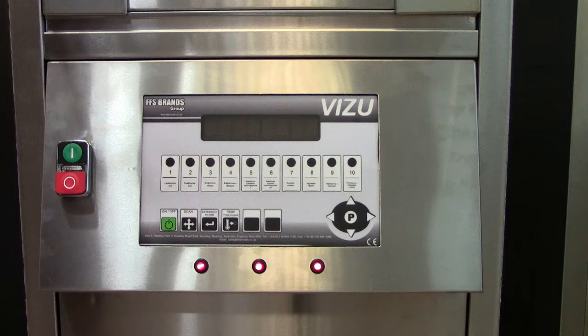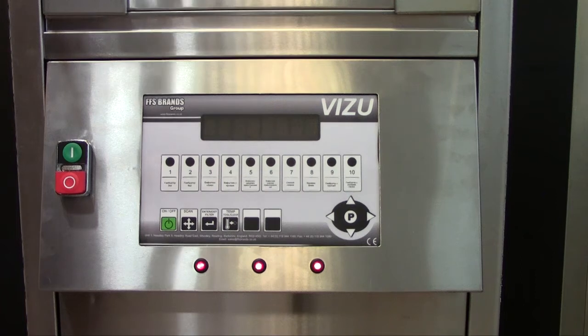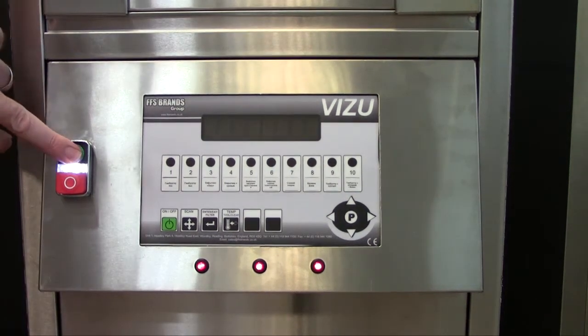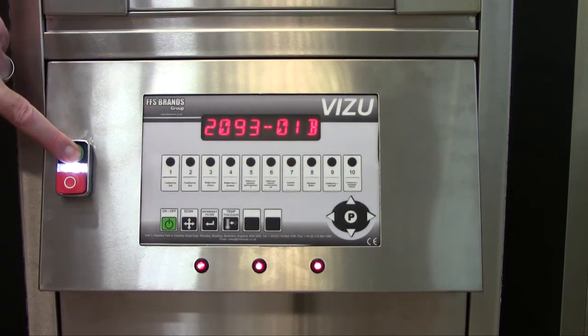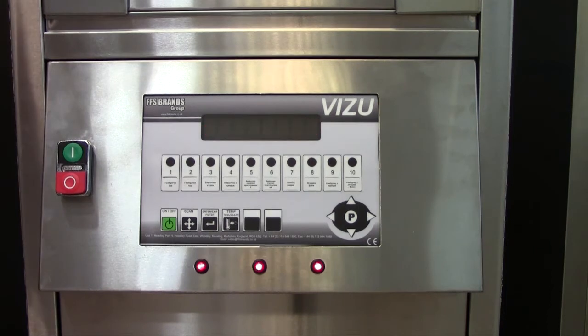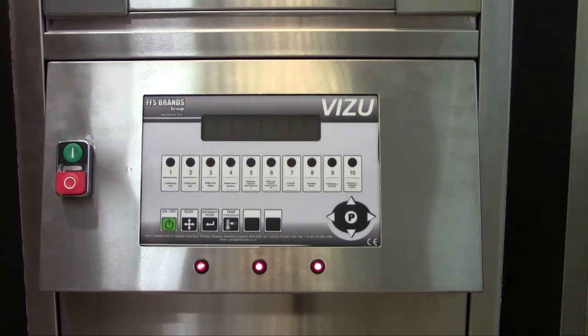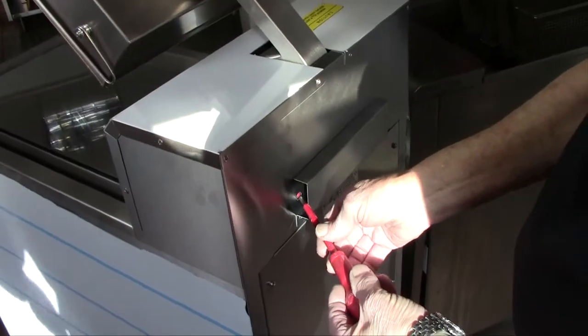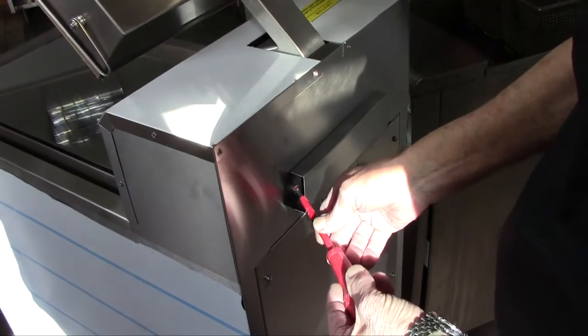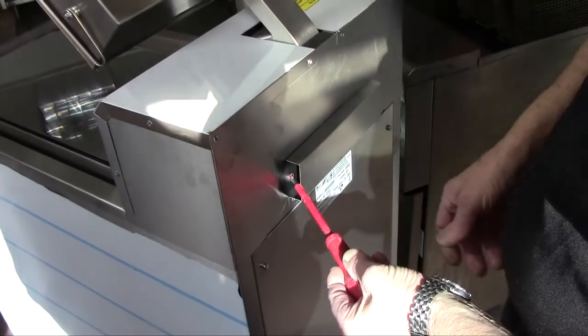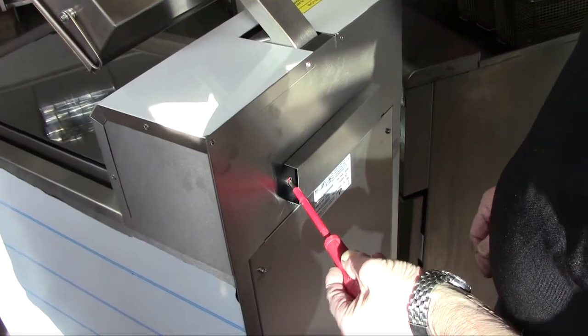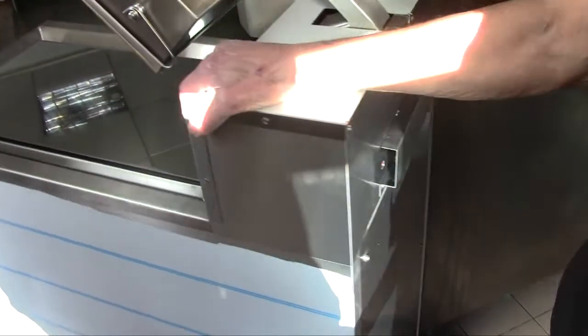If the problem still exists, as a check, press the start button, hold for 10 seconds and the display should come up. But on releasing it, if it goes out, then check the high limit stat at the back of the machine. Reset the high limit stat that is at the back of the machine. It can be reached with a screwdriver. You press the screwdriver in, go to the front and see if the machine starts.